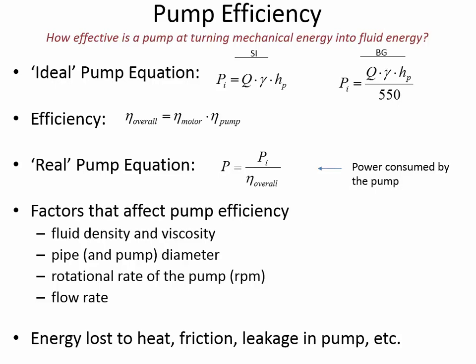Now, efficiency varies not only from pump to pump, but even one given pump may have different efficiencies depending on what flow rate you're operating it at, what speed the motor is spinning, or how high it's having to lift the water. And so one of the big jobs for engineers selecting pumps is to go through page after page of efficiency diagrams and try to pick out the pump that has the highest efficiency at the conditions you expect it's going to work at.